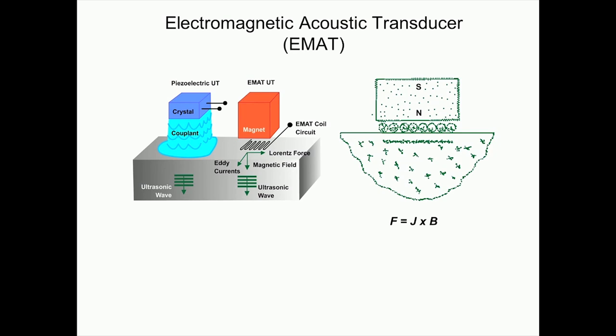So, that kind of transducer, the working principle is also different compared to a normal ultrasonic transducer, and these are known as electromagnetic acoustic transducers, because as I am going to show you now, this is based upon electromagnetic induction. So, as you could see in this case, when you have a normal piezoelectric ultrasonic transducer, you need to use this couplant to avoid that air gap, and in this case you do not really have to make a contact between the transducer and the sample, because in this case the ultrasonic waves are generated through electromagnetic induction, and that is why this kind of probes are known as electromagnetic acoustic transducers. Okay. So, let us see what is the working principle of this kind of transducer, how do they work, and what is the difference between them and the normal piezoelectric transducers.